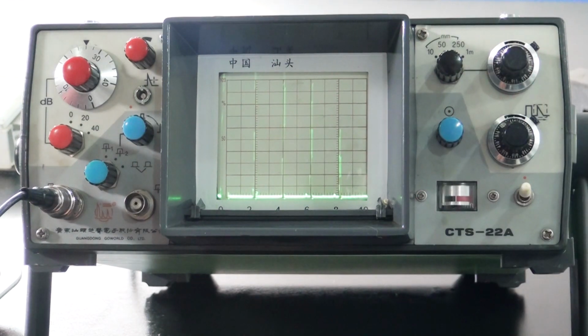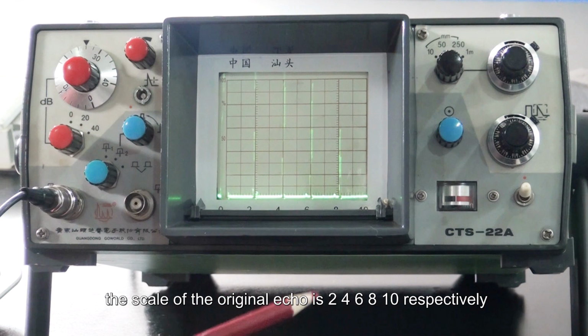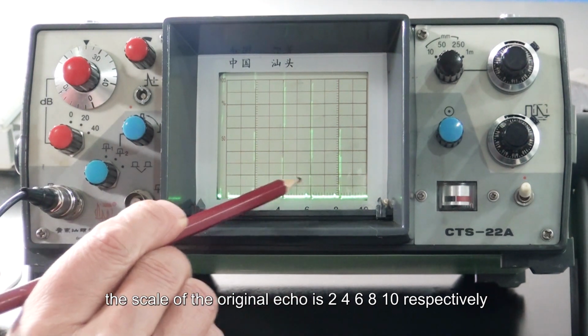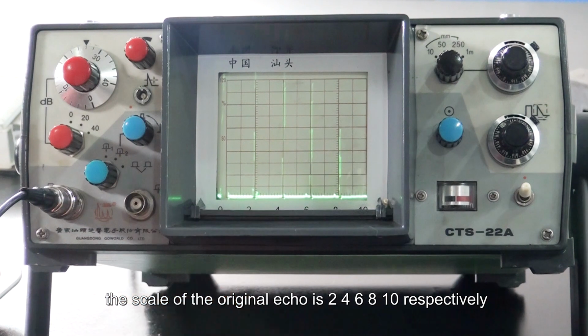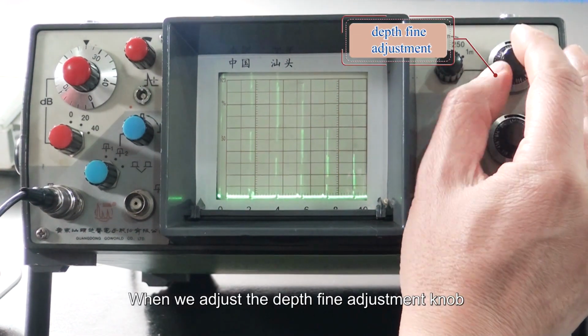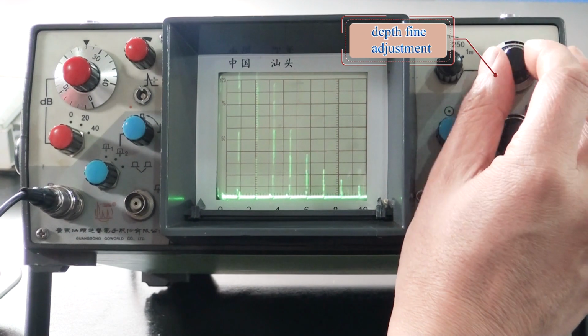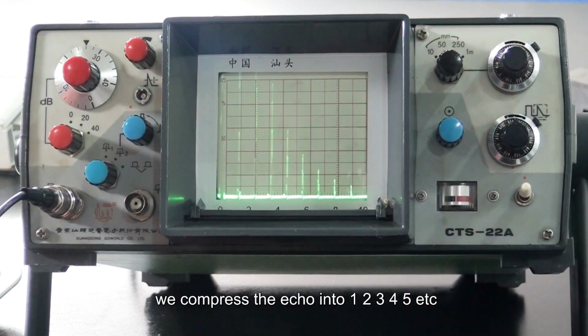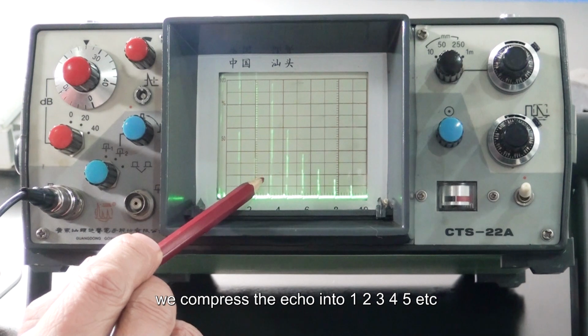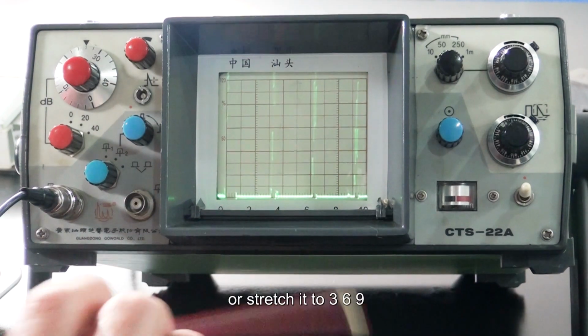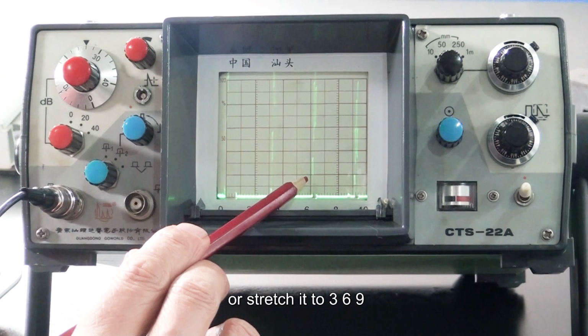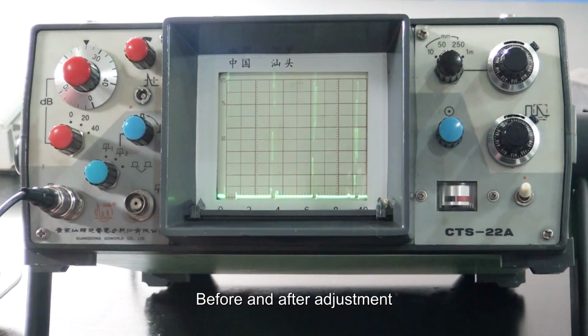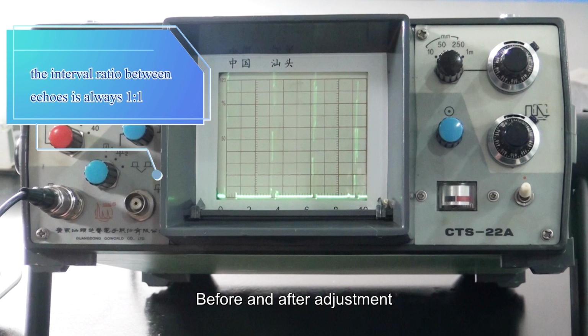For example, the scale of the original echo is 2, 4, 6, 8, 10 respectively. When we adjust the depth fine adjustment knob, we compress the echo into 1, 2, 3, 4, 5, etc., or stretch it to 3, 6, 9. Before and after adjustment, we will find that the interval ratio between echoes is always 1:1.